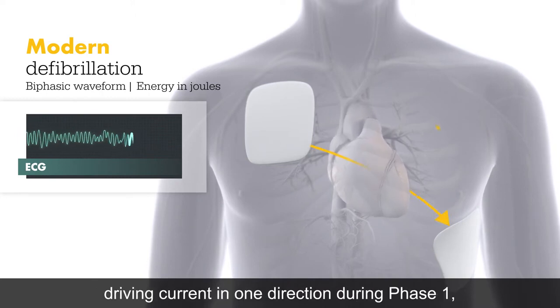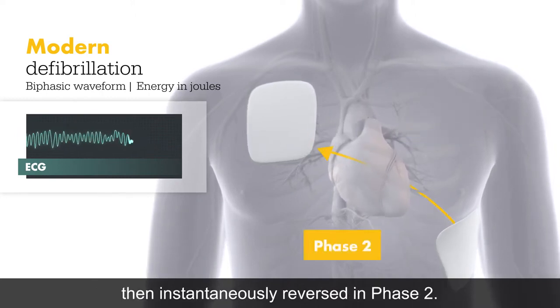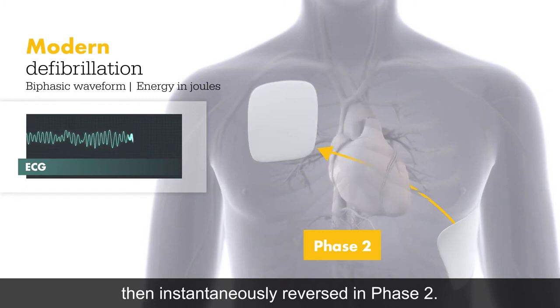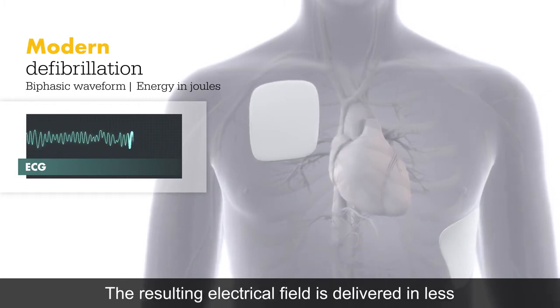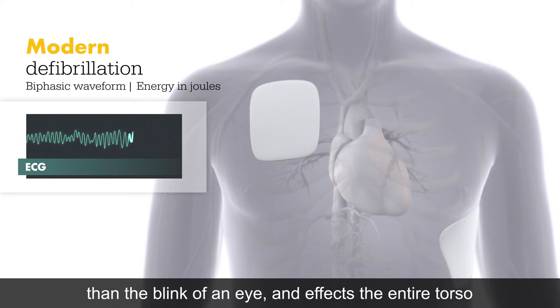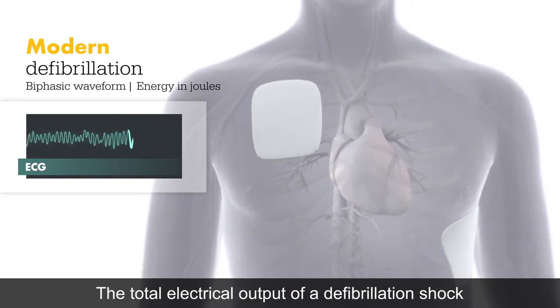Voltage is applied to the body for a specific time, driving current in one direction during phase one, then instantaneously reversed in phase two. The resulting electrical field is delivered in less than the blink of an eye and affects the entire torso.